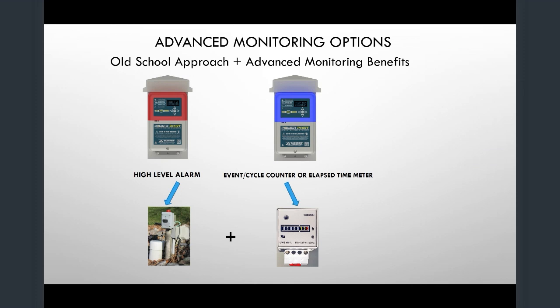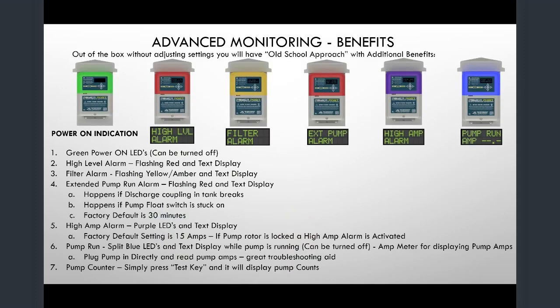You'd have your high level would be a red LED. Your pump run would be blue. Your green is your system normal. Red is high level. Amber or yellow would be filter alarm. The red and blue would be extended pump run alarm.